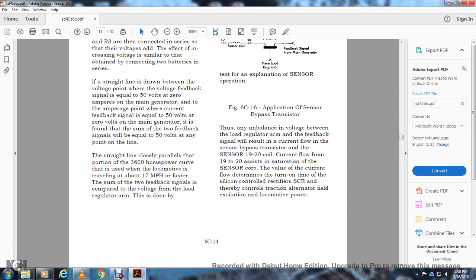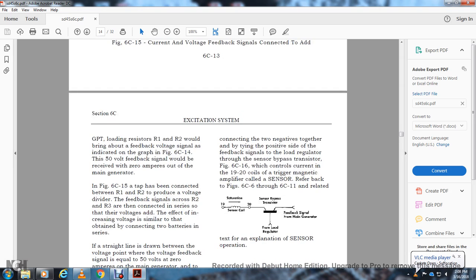it is found that the sum of the two feedback signals will be equal to 50 volts at any point on the straight line, closely parallel to the 3600 horsepower curve. The locomotive is traveling at 17 miles per hour or faster. The sum of the two feedback signals is compared to the voltage from the load regulator arm, this is done by connecting the two negatives together, then tying to the positive side of the feedback signal of the load regulator through the sensor bypass transistor. Figure 6C-16 will control the current in the 19 and 20 coil of the trigger magnetic amplifier sensor.